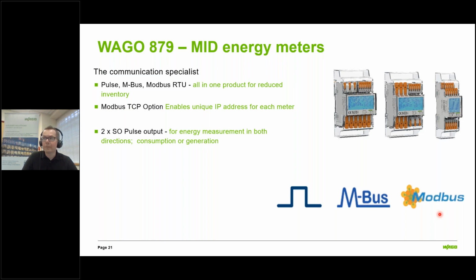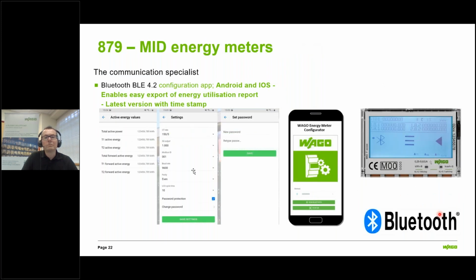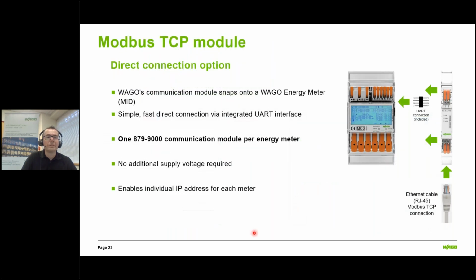Or we now also have an option to connect with Modbus TCP, which is an Ethernet-based solution enabling individual IP addresses for each meter. We can also export very conveniently, which is actually quite a unique feature for the WAGO meter, using a Bluetooth connection and an app on either an Android or iOS device, so that you can download meter readings. Now, if you were a landlord and needed to take meter readings of tenants' bills, that could be very convenient and would also give evidence of where the meter reading was derived. The optional Modbus TCP unit simply snaps onto the side of the meter, so you have a one-to-one relationship of the IP address to individual meters.